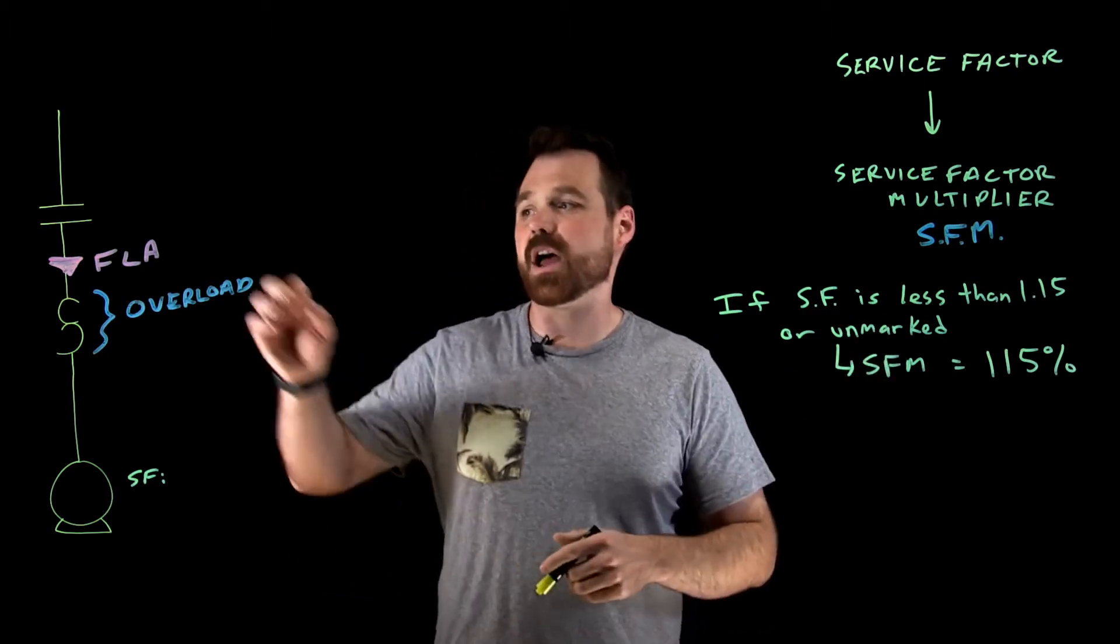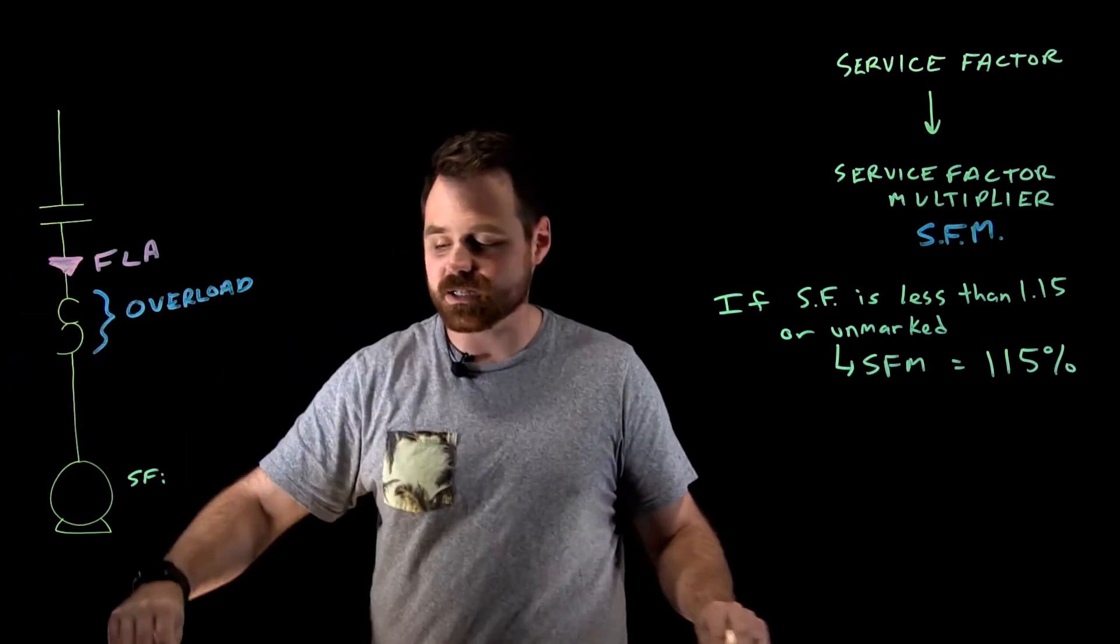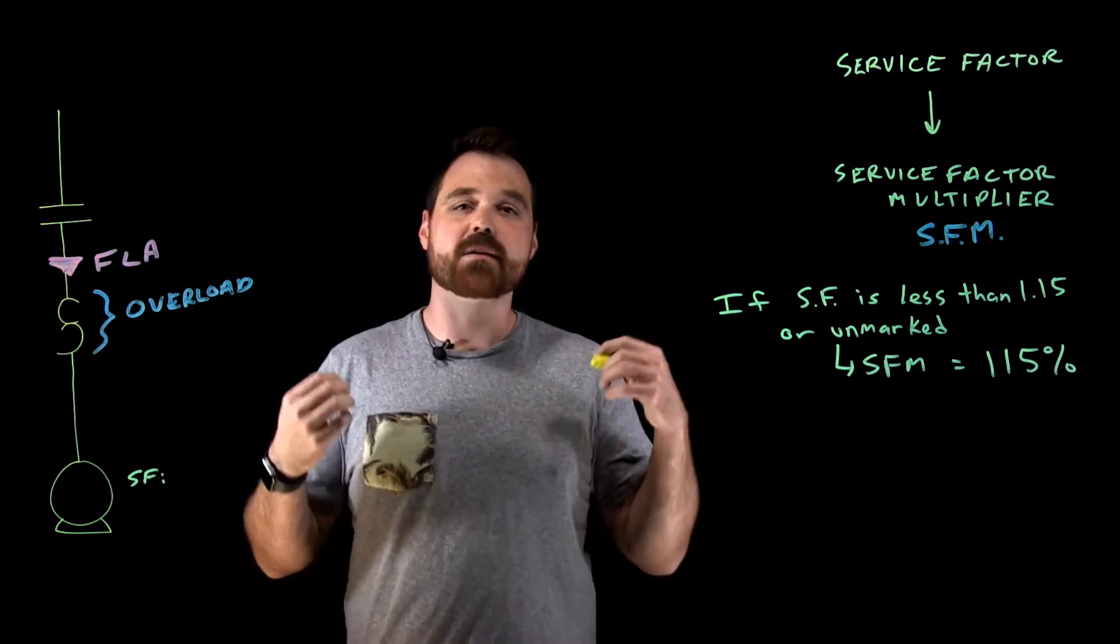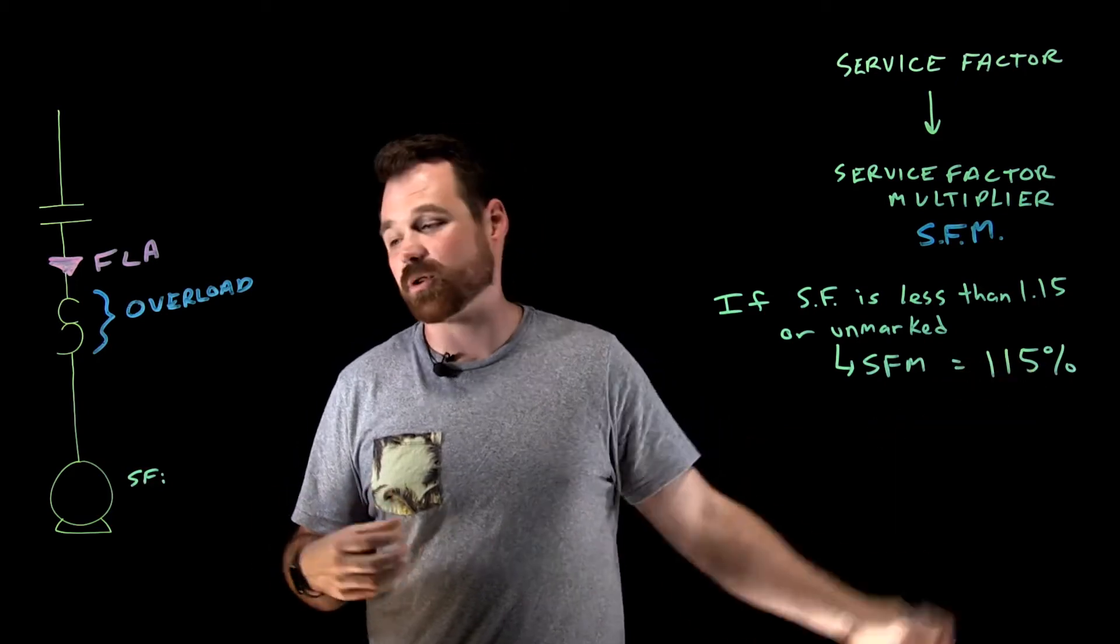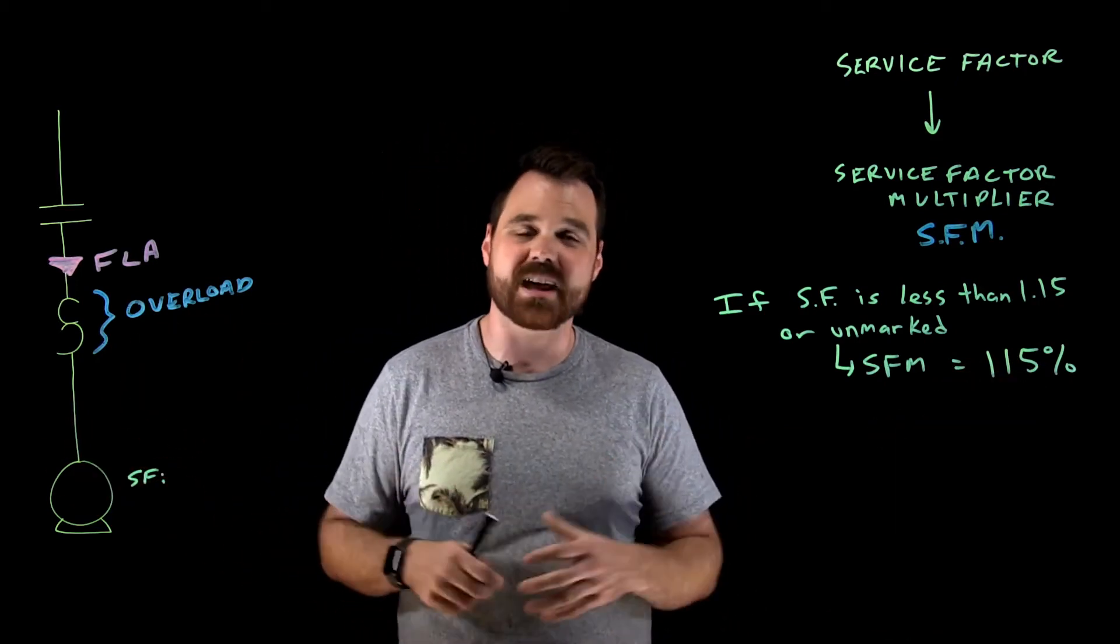So my service factor is marked less than 1.15. I'm going to use 115% as my service factor multiplier. So I would take my FLA or whatever current is going to be running through that overload device. I take that current and I multiply it by 115%, and that is what I would set my overloads at. And that's my maximum allowable setting.